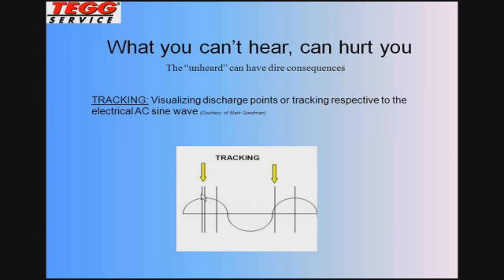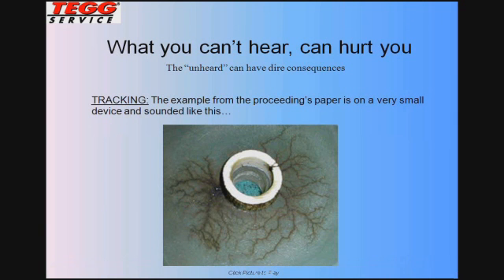So that helps correlate what we're seeing in the time domain as far as what type of anomaly we may be dealing with. Now, those amplitudes and the compact nature of the excursions are going to change even on known samples depending on the severity of the tracking. And the reality is, ultimately, tracking will degrade and turn into full-blown arcing, and that's typically right before a failure. So we want to find this early. There's another sound file here just from a molded case circuit breaker that we recorded over in the UK.